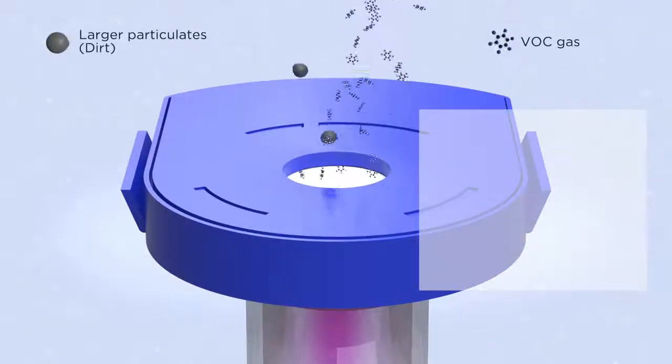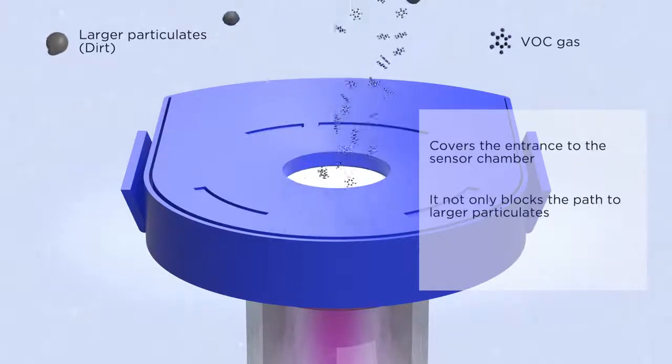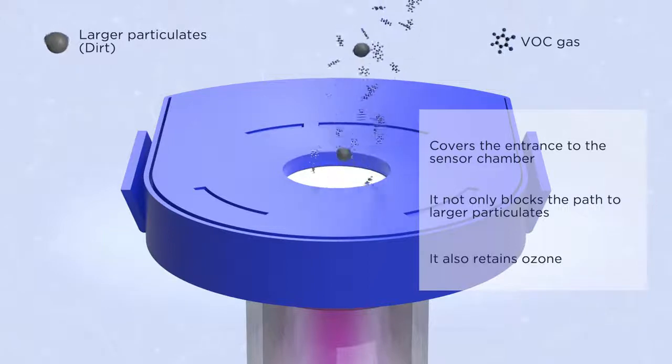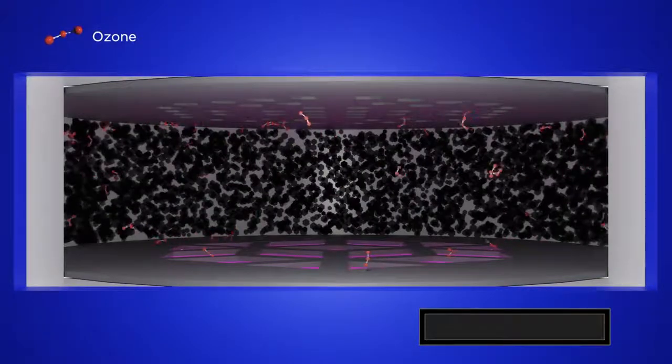Our anti-contamination system consists of a fine woven PTFE membrane that covers the entrance of the sensor chamber. It not only blocks the path to larger particulates, it also retains ozone that is naturally generated in the sensor chamber. Ozone aggressively cleans the chamber and lamp window, helping maintain optimal performance over extended periods.